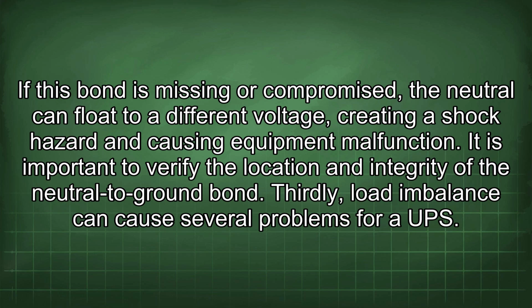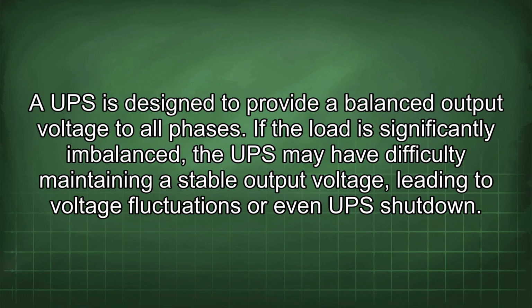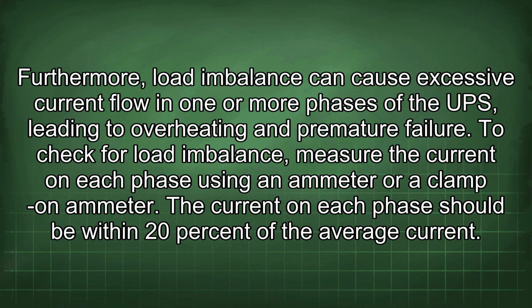Thirdly, load imbalance can cause several problems for a UPS. A UPS is designed to provide a balanced output voltage to all phases. If the load is significantly imbalanced, the UPS may have difficulty maintaining a stable output voltage, leading to voltage fluctuations or even UPS shutdown. Furthermore, load imbalance can cause excessive current flow in one or more phases of the UPS, leading to overheating and premature failure.